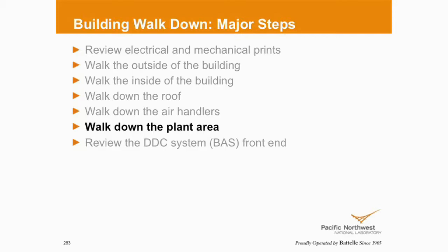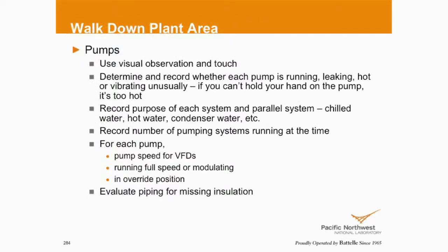Walk your plant. Look at your pumps. Are they running? Are they vibrating? Are they excessively hot? Are they in parallel? Are they parallel piped pumps with VFDs? Fans and VFDs and pumps that are in parallel: huge opportunity for the affinity laws, cube savings. A lot of people don't like to run them in parallel, because if I've got two pumps, two fans, you want me to run them both? What if one fails? Well, the other one will just pick up speed. But yes, you just lost your backup. But there can be significant energy savings running parallel.